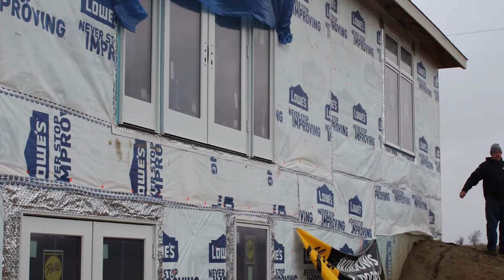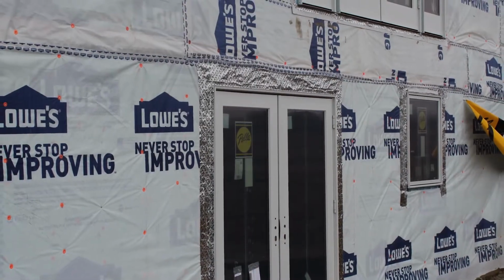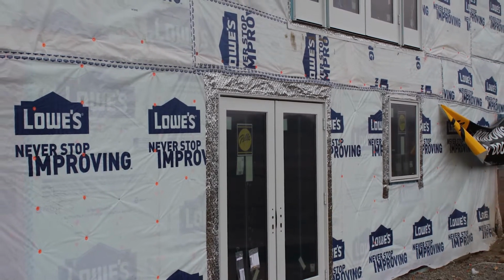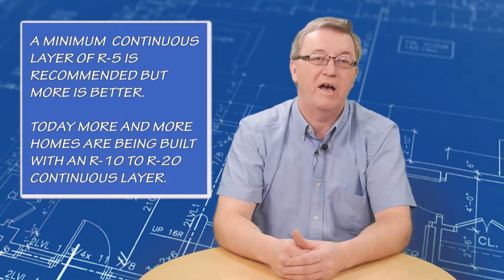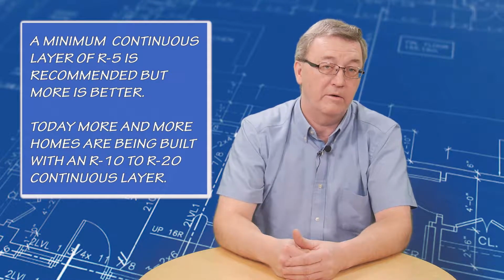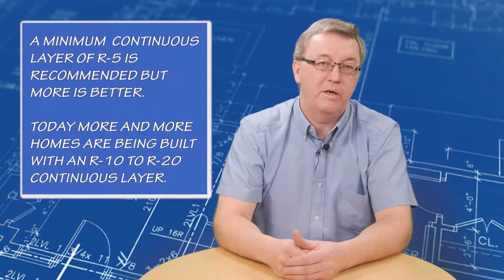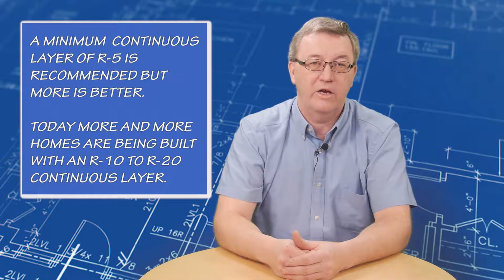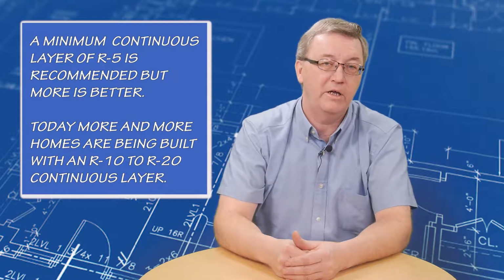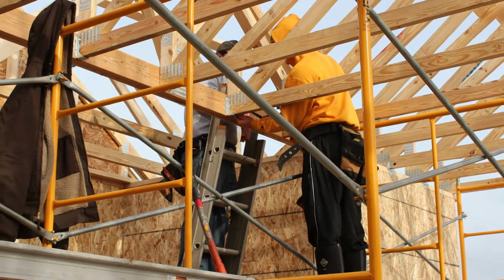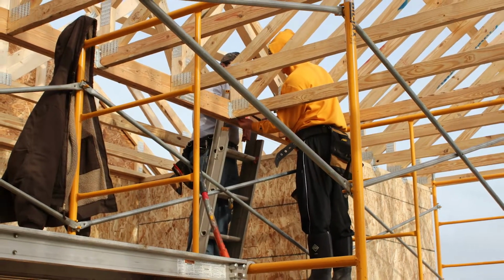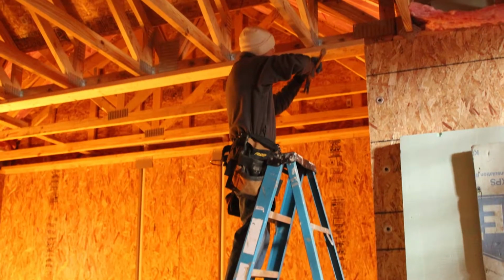In addition to the air seal, it is important to have a continuous insulation layer on the exterior of the wall. The more continuous insulation versus cavity insulation, the higher the average R value of the wall becomes. For our weather zone, a minimum continuous layer of R5 is recommended, and the more, the better. Today, more and more homes are being built with an R10 to an R20 continuous layer. Having this continuous layer provides a complete thermal break between conditioned and unconditioned space. Along with reduced framing material and better wall configuration, this increases the overall R value of the wall, greatly reducing conductive losses from the building.